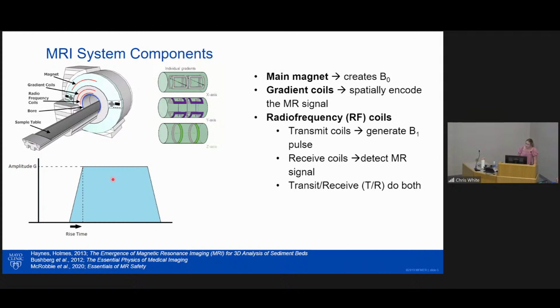And then the third component is the radio frequency coils, or the RF coils. And RF coils can be split into transmit or receive coils. So transmit coils generate the radio frequency pulse, or RF pulse, also called the B1 pulse. And then receive coils detect the MR signal. And then transmit-receive, or TR, coils do both.